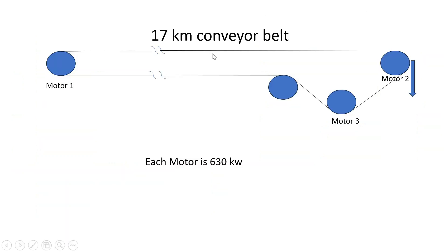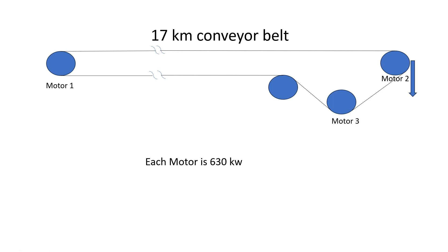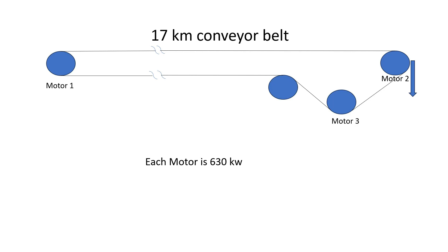But in our case it is very critical — it is a 17 km conveyor belt and the cost is high. So you have to control precisely. There is another parameter named 'add mode'. You know torque mode and speed mode — the third mode is add mode. So you can run the Master-Follower drive in three ways: torque mode, speed mode, and add mode.